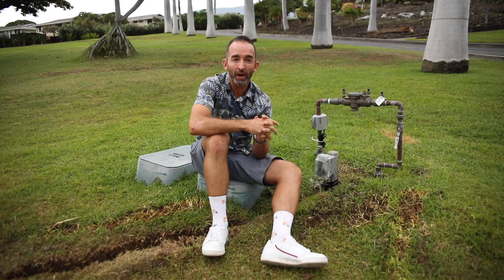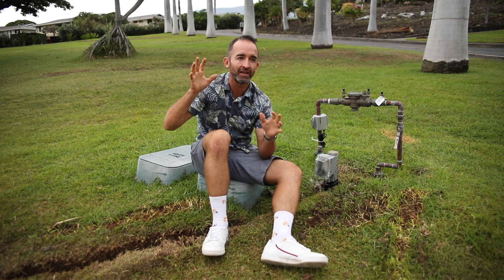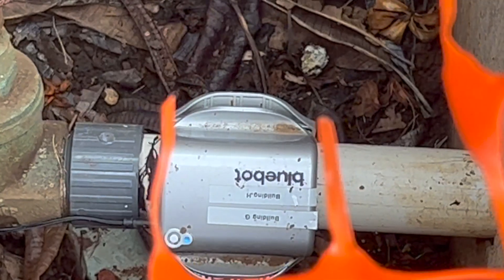BlueBot is helping us identify where we have leaks on campus. Historically we've found a number of larger leaks, and now we're getting to the point where we've tackled the low-hanging fruit. BlueBot is helping us have a more granular, more micro-focus on each of our buildings and smaller areas on campus, so that we can monitor overnight flows, because we have minute-by-minute data now. We can check the low midnight flows, see if we're having consistent flow rates, and that allows us to identify consistent leaks for further investigation.